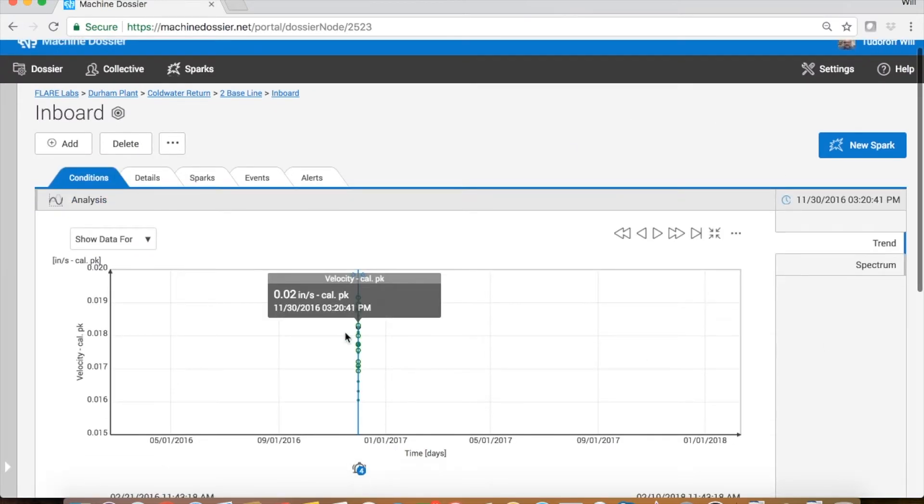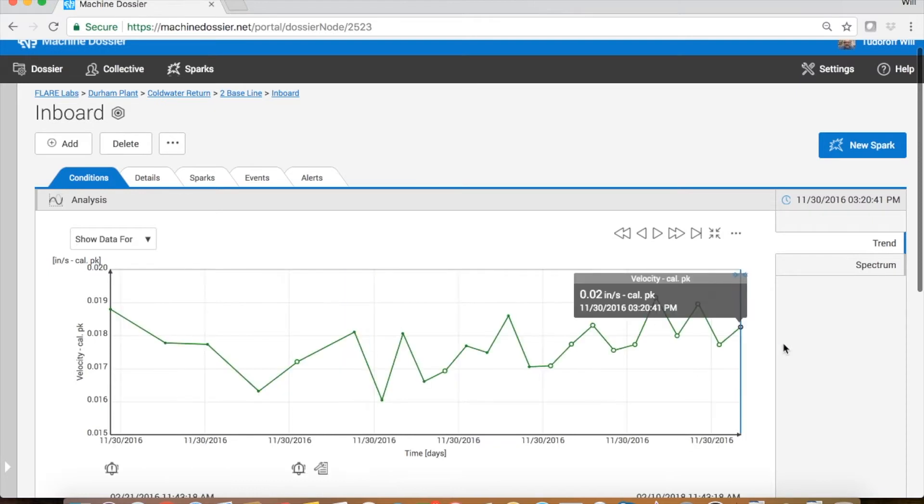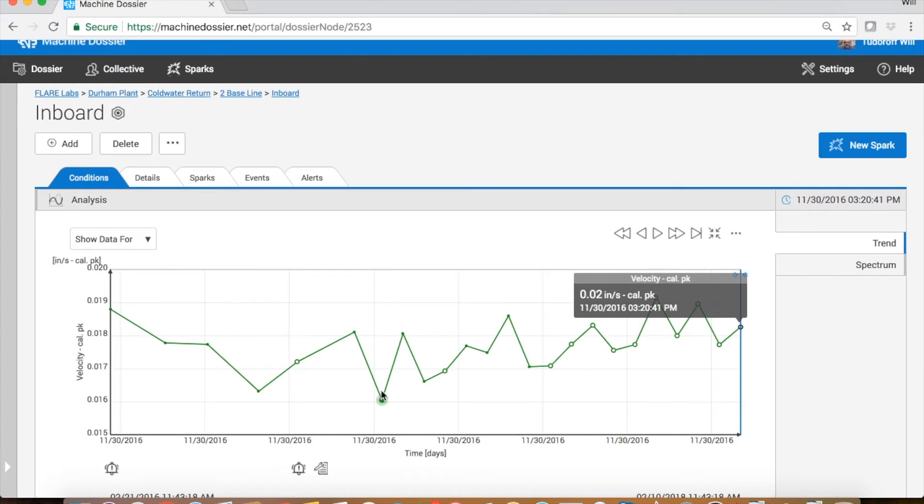First thing we'll do is zoom in on that day that we did the baseline and we see that the data fluctuated between 0.016 inches per second and 0.02 inches per second. That's an overall vibration value.